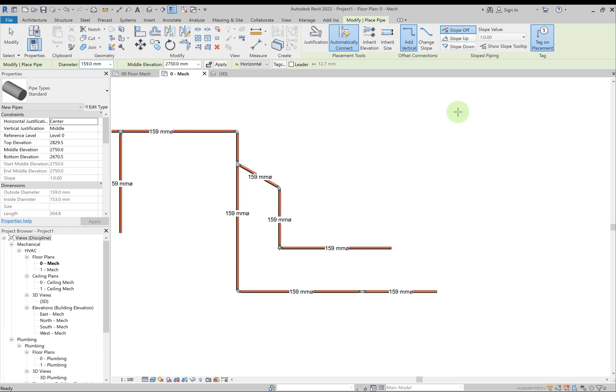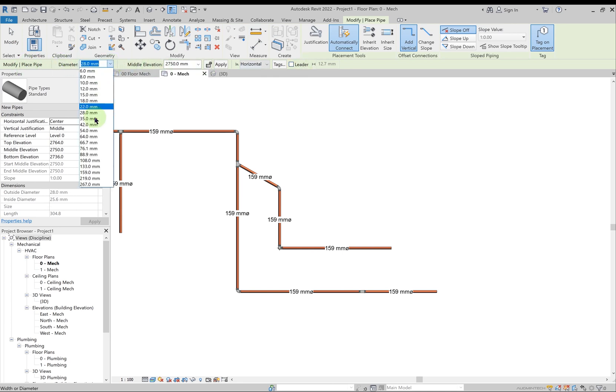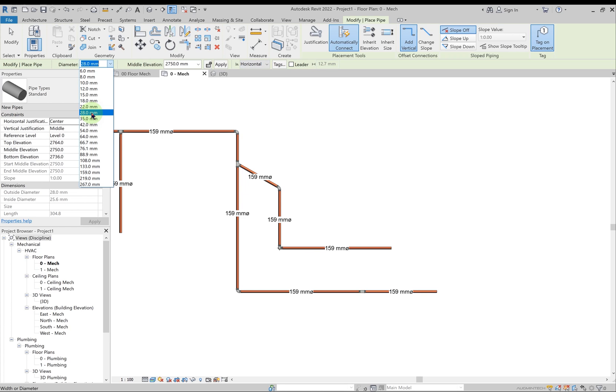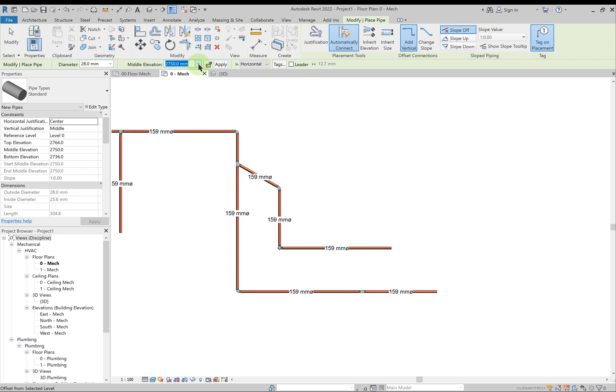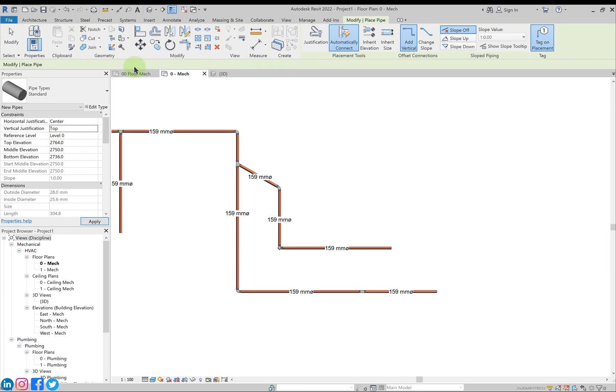Let's click Slope Off and discuss the options bar, which only appears once you've activated the pipe command. Here you can see a list of options with different diameters to select from. If you want a diameter not available, make changes in pipe settings. Then you have the middle elevation. If you want to define the top elevation instead, go to Vertical Justification and change from Middle to Top — the option changes to top elevation.